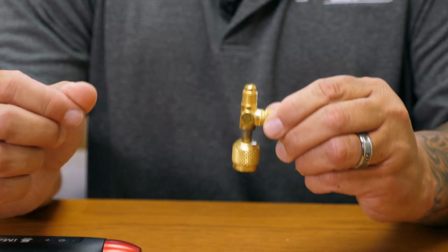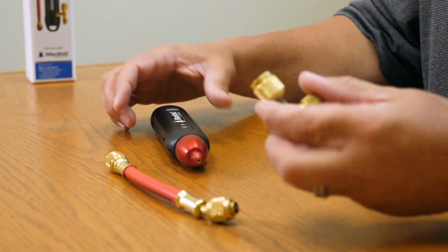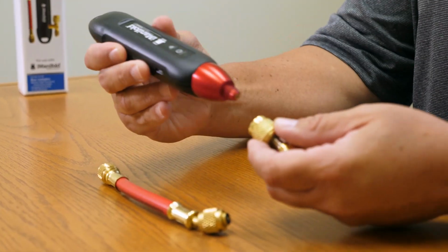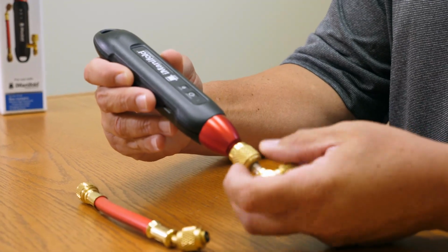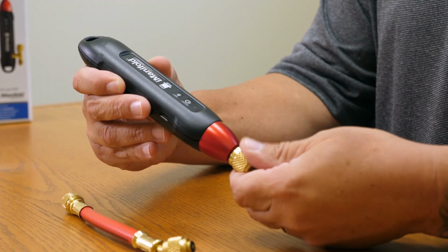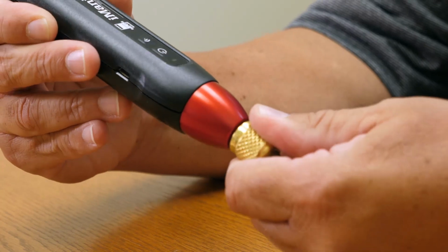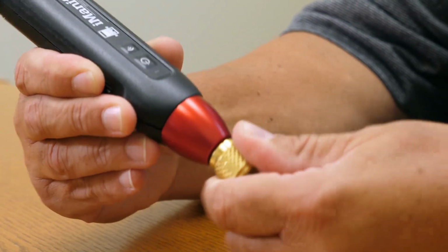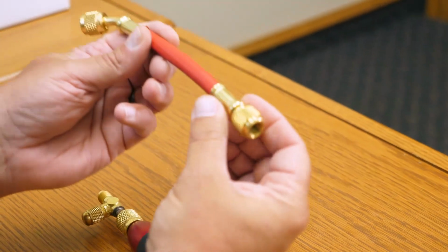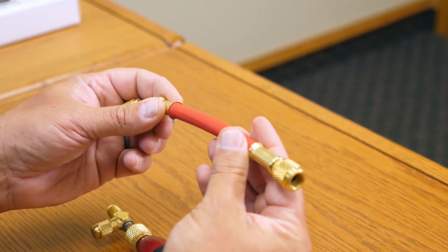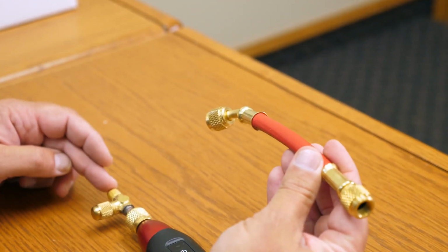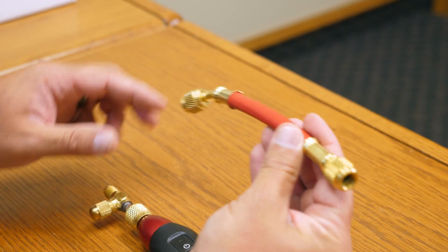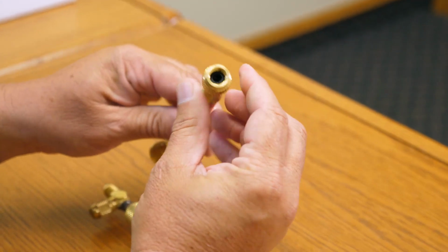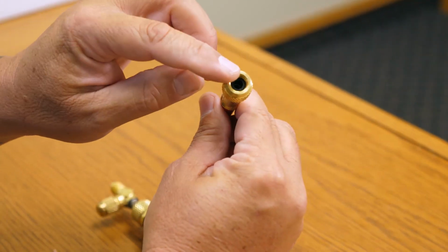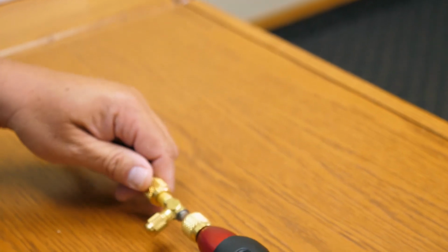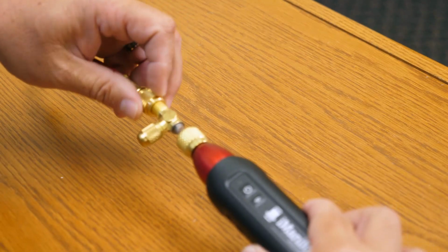Now we're ready to install the rest of the probe: install the access valve on the probe itself. Use this thumb nut, bring it down, and firm it up pretty good. Make sure when you attach the hose that you put the right side onto the end of the access valve — the end of the hose on the straight side does not have a core depressor, and that's the side we're going to use to attach to the access valve.